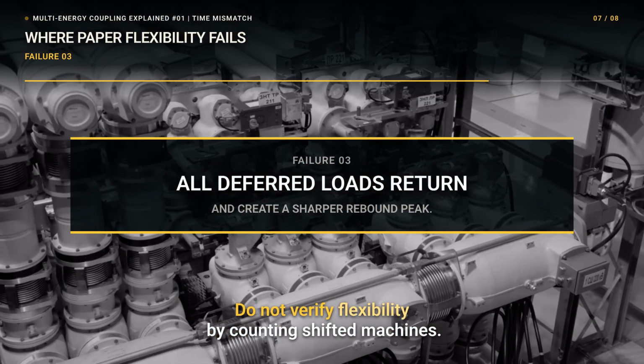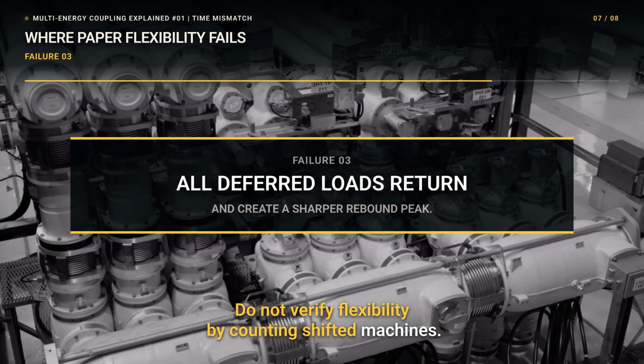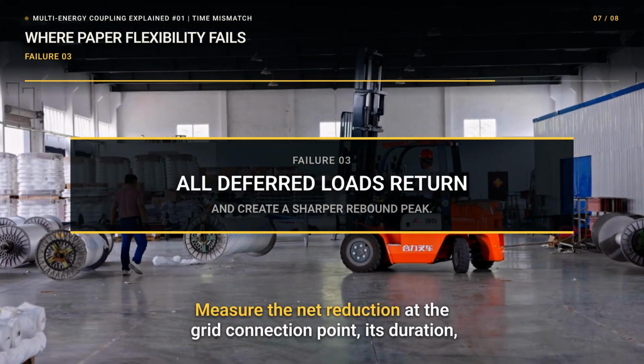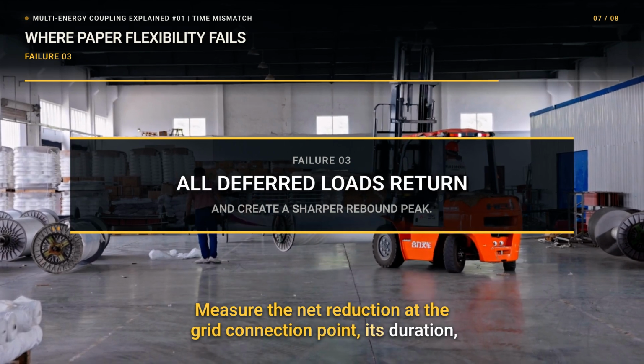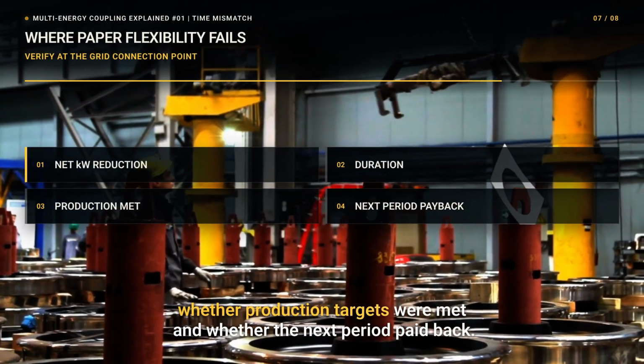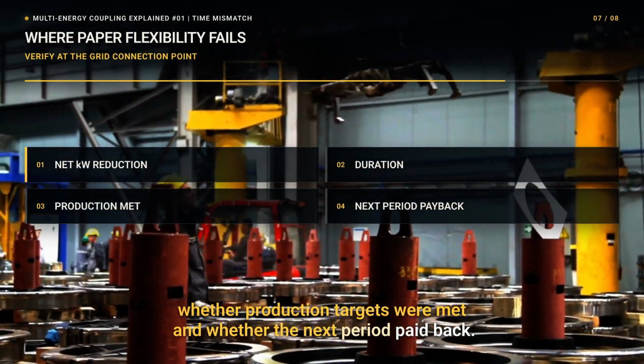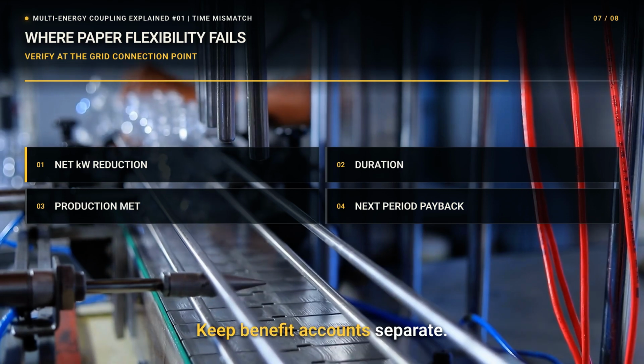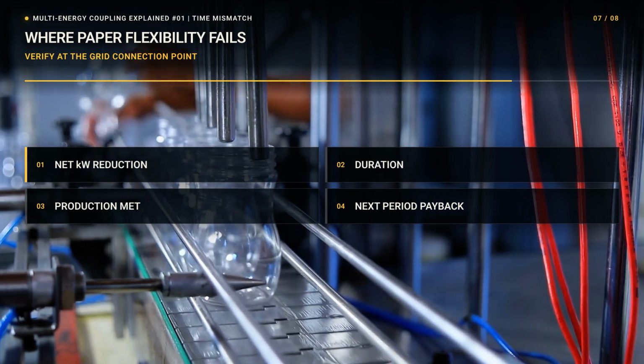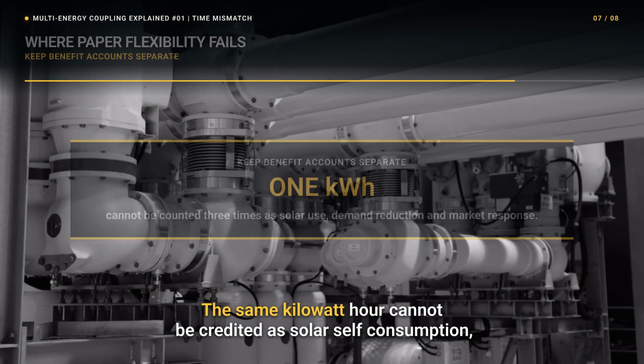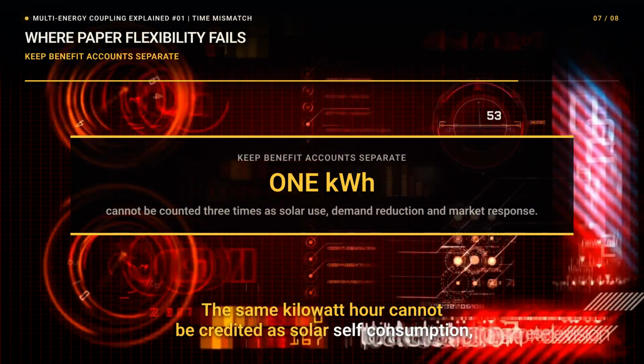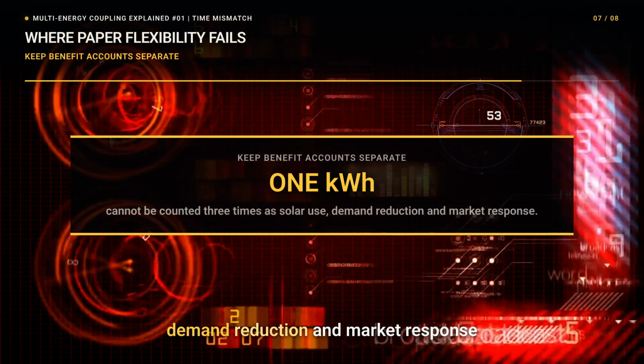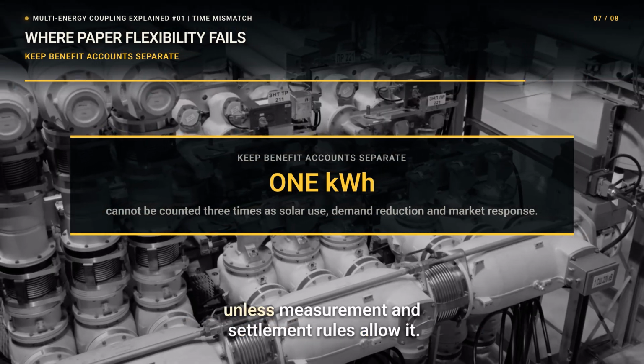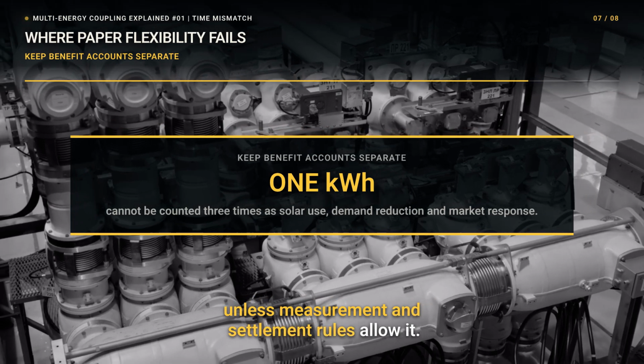Do not verify flexibility by counting shifted machines. Measure the net reduction at the grid connection point, its duration, whether production targets were met, and whether the next period paid back the apparent saving. Keep benefit accounts separate. The same kilowatt-hour cannot be credited as solar self-consumption, demand reduction, and market response unless measurement and settlement rules allow it.